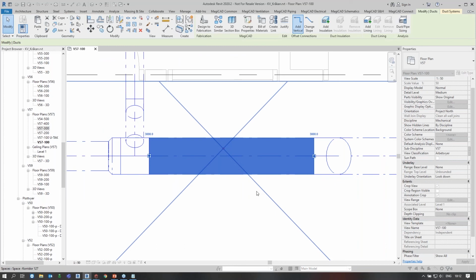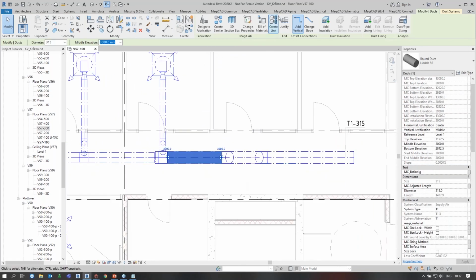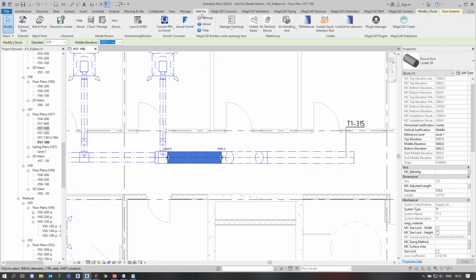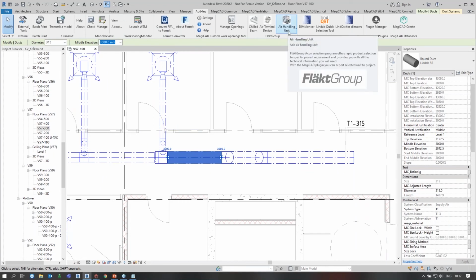Let's check the sound now too. We have a couple of plugins from air handling unit manufacturers - here I have one from FläktGroup. They have air handling unit software on the web that creates a DXF file, and with this plugin you can convert that DXF file into a Revit family mechanical equipment. If I connect my duct to that machine, it transfers the sound data into my duct.